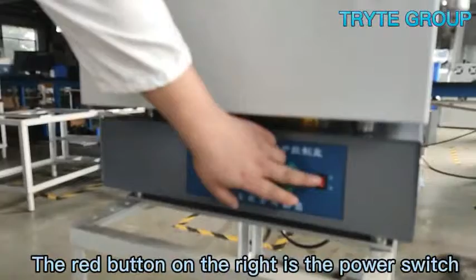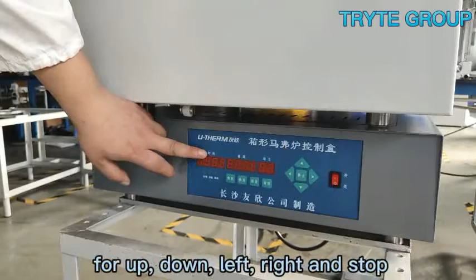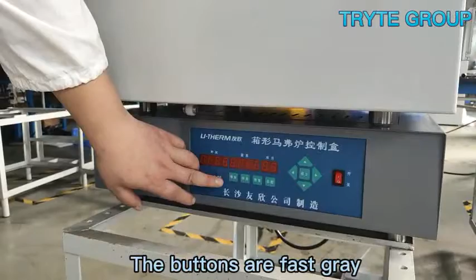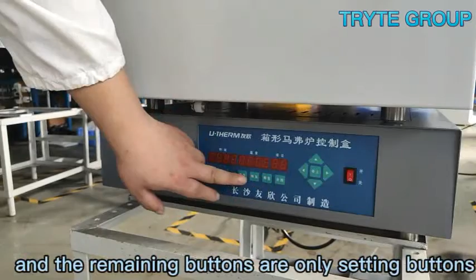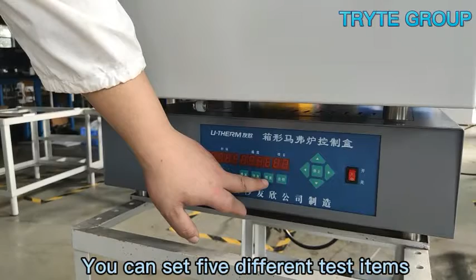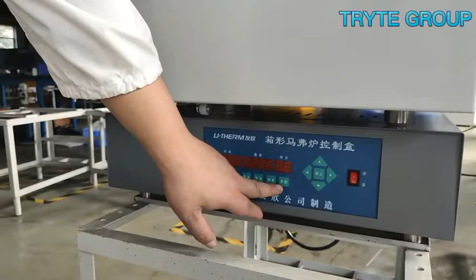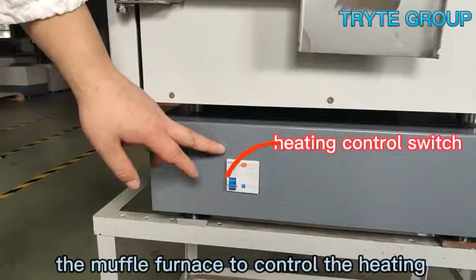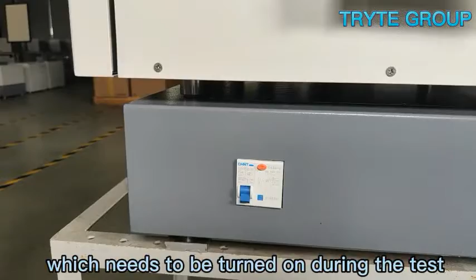Below the furnace is the control box of the muffle furnace. The red button on the right is the power switch. On the left of the switch are the buttons for up, down, left, right and stop. The buttons are fast ash, slow ash, and volatilization, and the remaining buttons are only setting buttons. You can set 5 different test items, and set the test time and temperature you need. There is a special switch on the right side of the muffle furnace to control the heating, which needs to be turned on during the test.